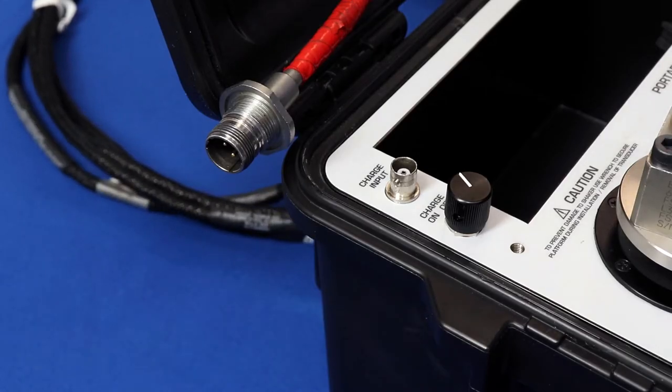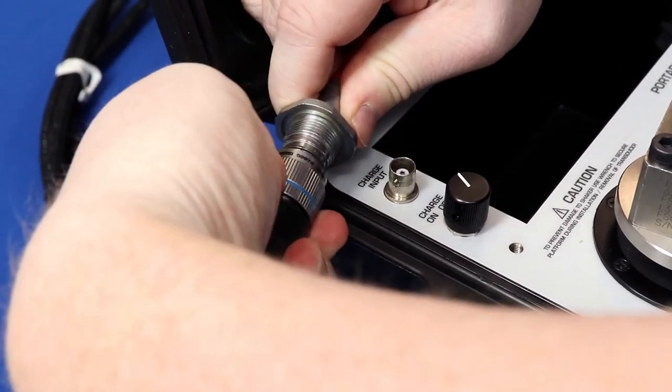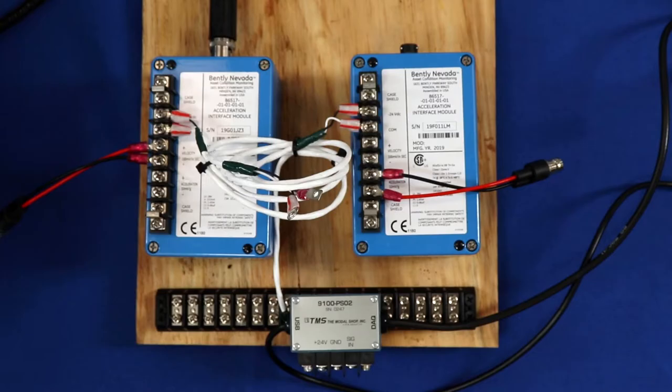Now that we have the accelerometer mounted, we need to connect the black cable to the two-pin connector on the end of the integral armored cable. We align the keyway and it snaps in place, then give it a good amount of force to press it down — it takes quite a bit of twisting to get that connector seated, and it clicks as you twist. We have two Bently Nevada 86517 vibration signal conditioning interface modules here; I'm using the one on the left. The output of the accelerometer connects to the top of the unit. Along the terminal strip there's a velocity output at 100 millivolts per inch per second, and I've connected spade lugs to a BNC female to connect that to the portable vibration calibrator.